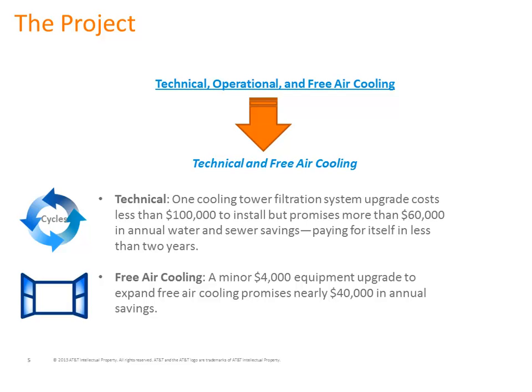So, for example, talking about making the business case for this, which is very important: we put in one cooling tower filtration system upgrade that cost less than $100,000 to install, but it's already returning more than $60,000 a year in annual water and sewer charge savings. So that's paying for itself in less than 2 years—pretty attractive payback. That's the dollar side.